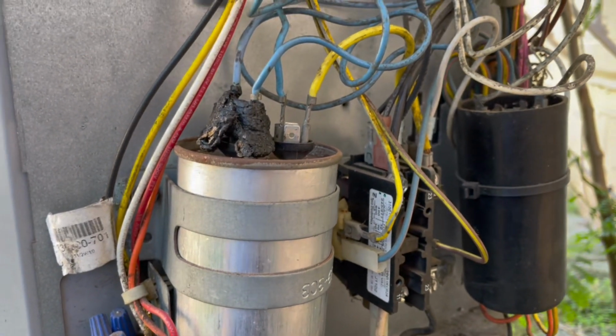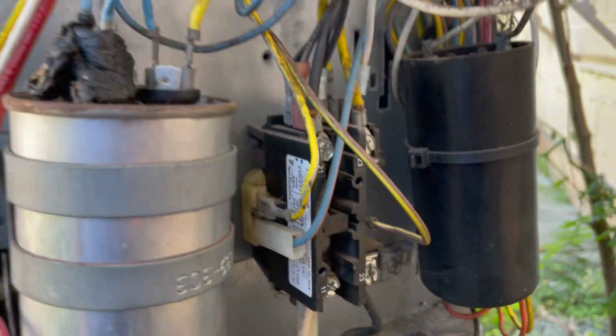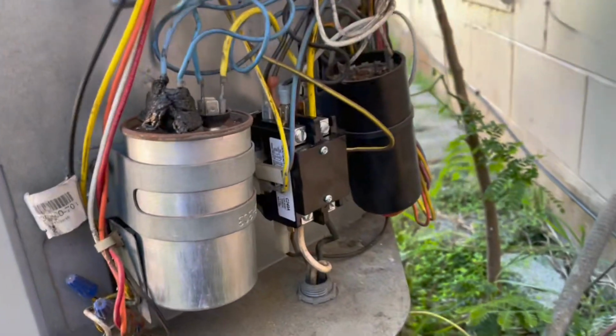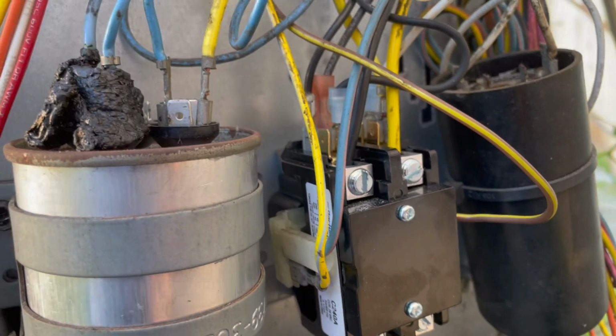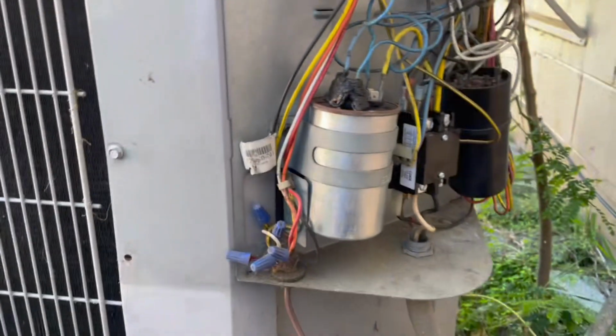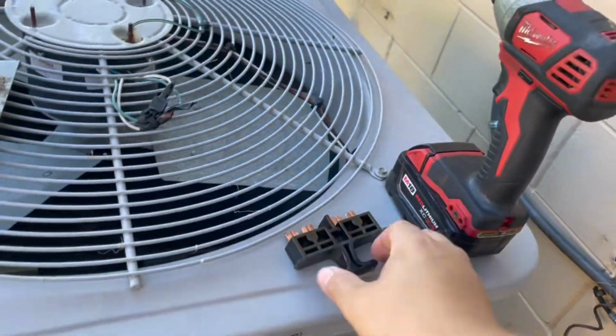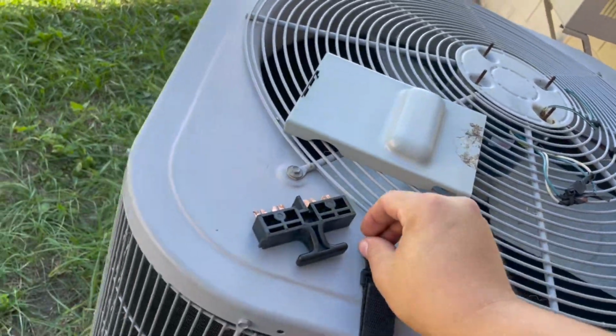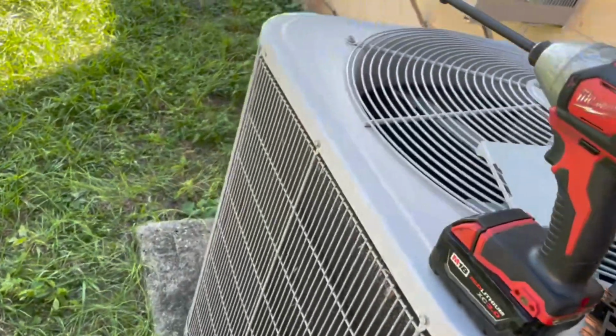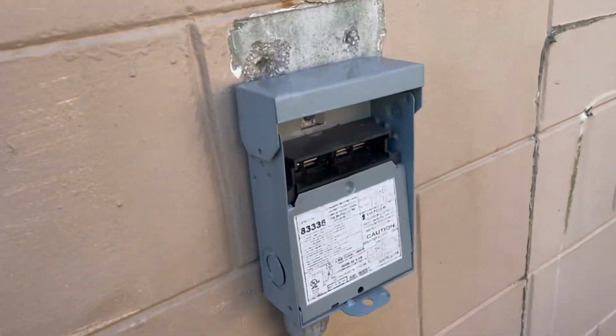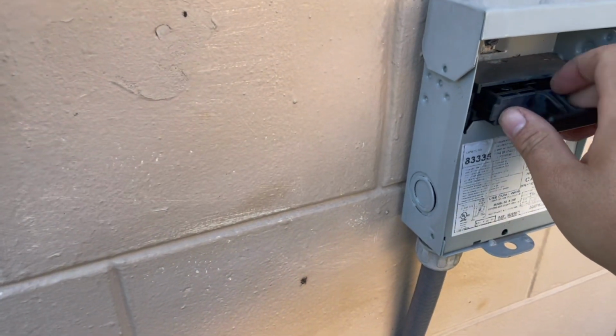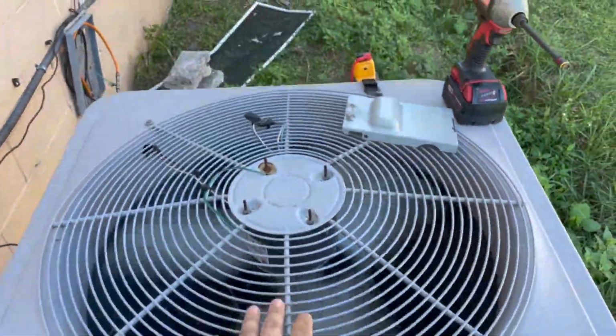And then he's got another system that it looks like it's low on refrigerant, but we're starting with this one. Okay, man, this is awful, but there we go. Contactor's changed out. Plug the low voltage back in. Now we're just gonna plug in the power, and as long as no one touched that thermostat inside, it should just turn on. Let's see. Hey, look at that. Okay, so unit's running. I'll let it run for a little bit.